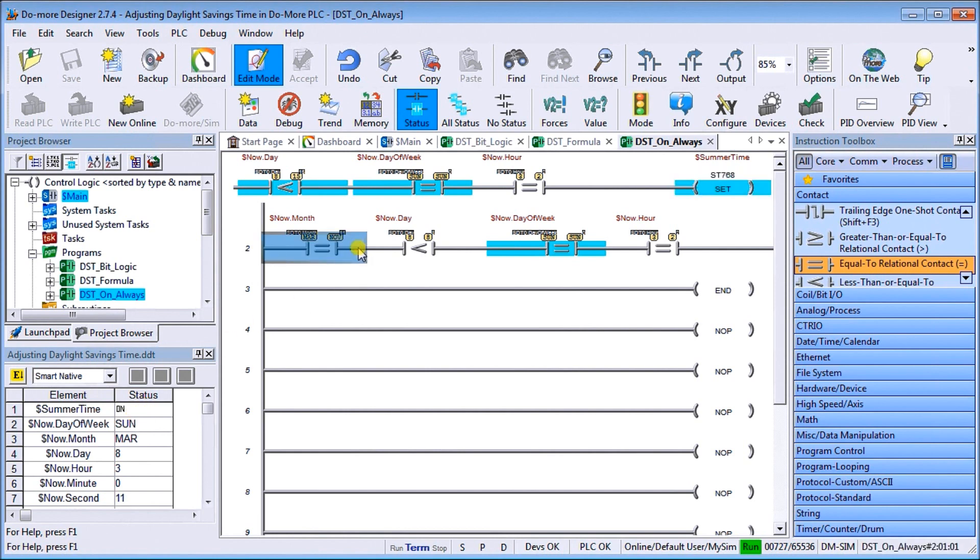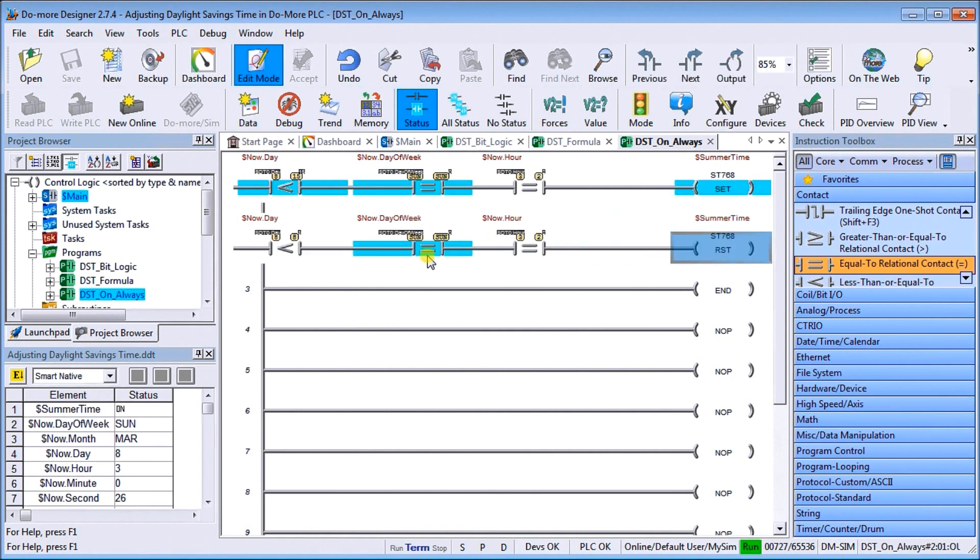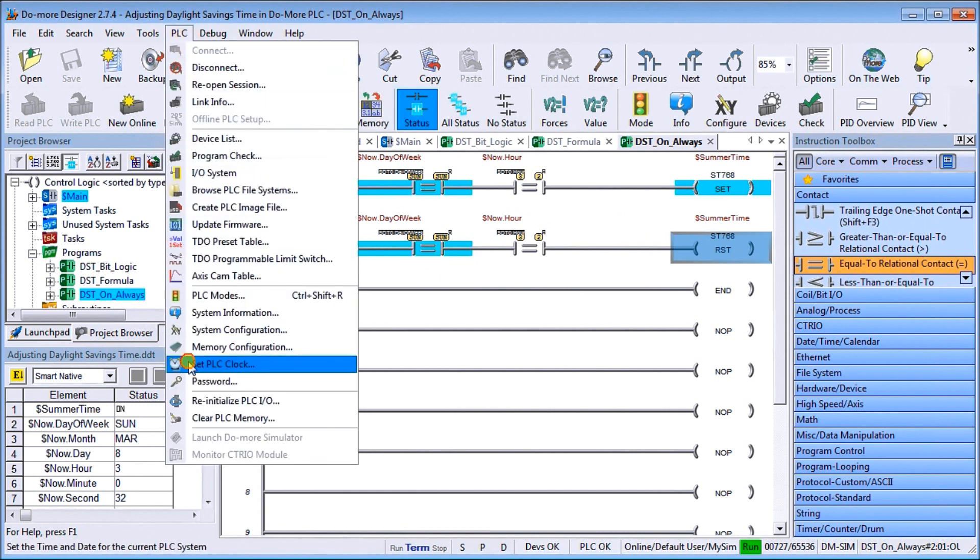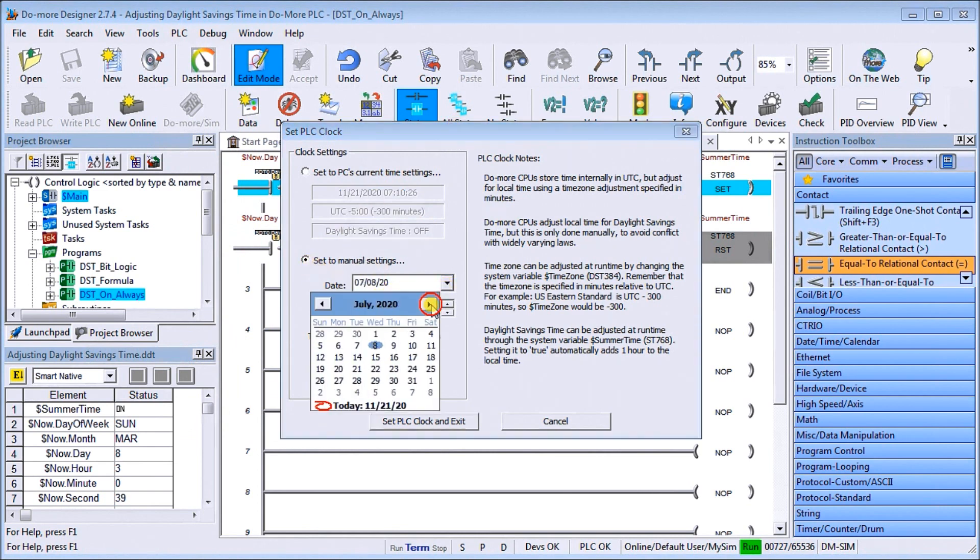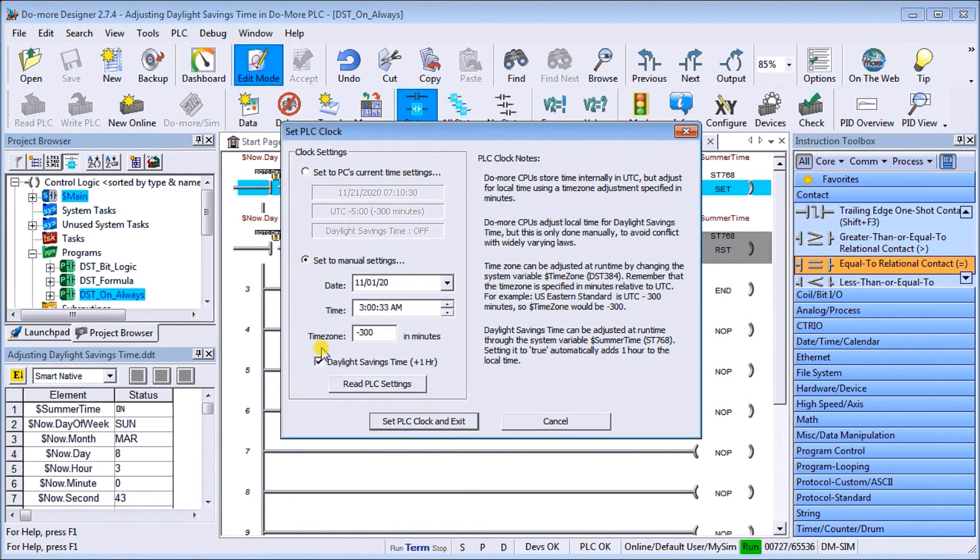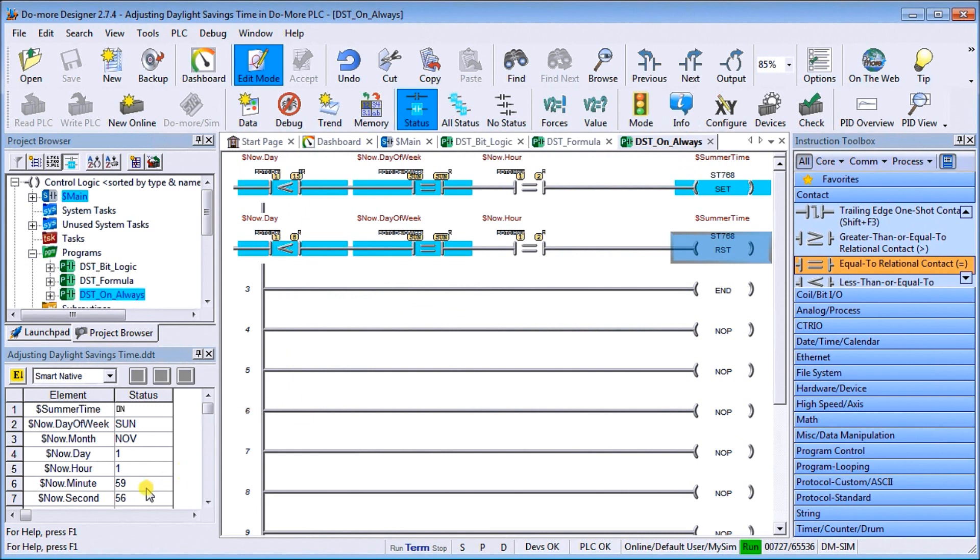The next rung of this, remember this is going to be always on, is going to look for November. And when we're less than eight so it's in the first week, we are Sunday and the hour is two, then what we do is we reset the summertime bit. So let's do that. PLC, set PLC clock, we'll do the manual settings. Now we'll go to November and we'll do the first of November. We'll set this at 1:59:55 and then we'll hit set the settings. Once we get to two o'clock then that setting now turns off, which is exactly what it did.